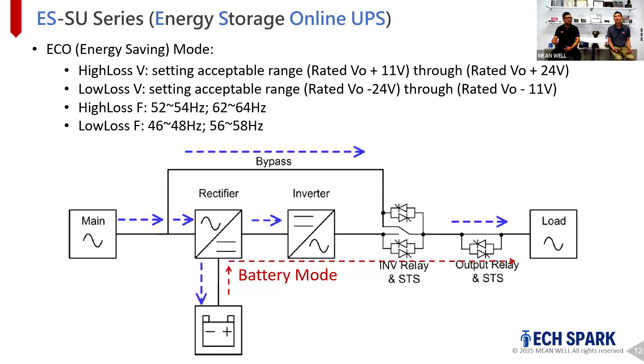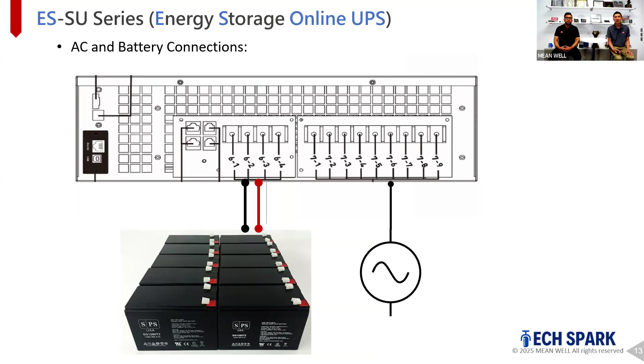Here is how you make the connection. It's usually provided with the terminal block. You see the battery - like I said, you have 10 to 20 of them stacked in series to make the high boost voltage. On the right hand side is the terminal block where you connect your AC power coming in. That's the AC and battery connection, and all the communication RS and some breakers are in the back of the unit.